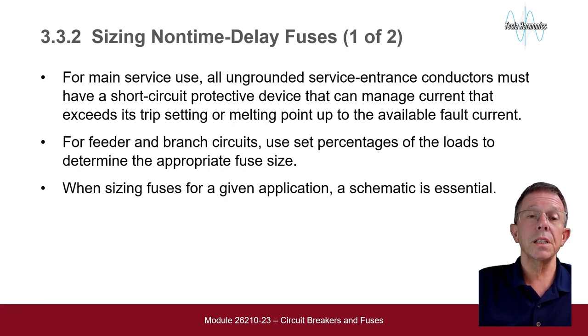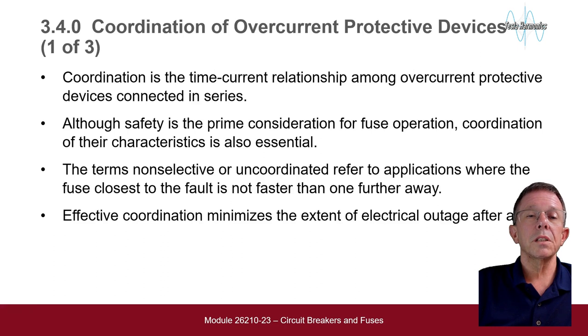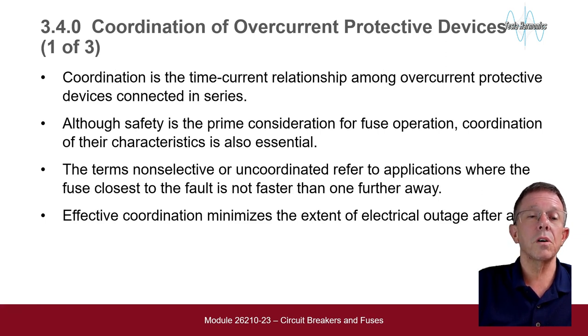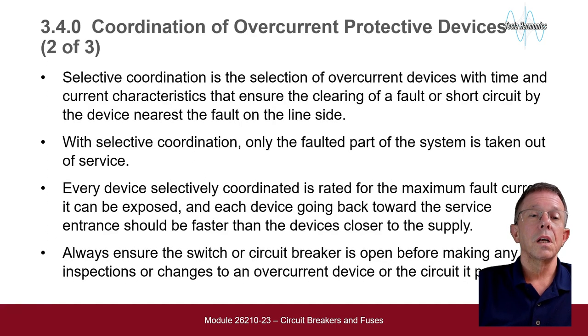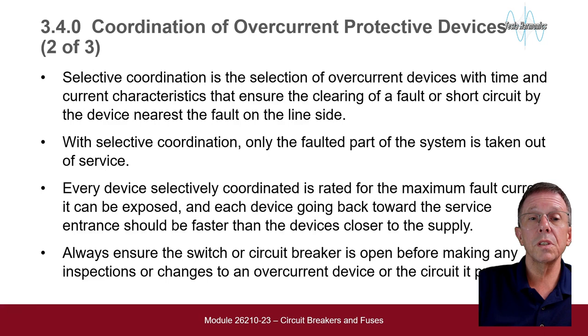Besides selecting the fuses for a given application, a schematic is essential. Coordination is a time relationship among overcurrent protective devices connected in series. Although safety is the prime consideration for fuse operation, coordination of their characteristics is also essential. The term non-selective or uncoordinated refers to applications where the fuse closest to the fault is not faster than one further away. Effective coordination minimizes the extent of electrical outage after a fault. Selective coordination is a selection of overcurrent devices with time and current characteristics that ensure the clearing of a fault or short circuit by the device nearest the fault on the line side. With selective coordination, only the faulty part of the system is taken out of service. Every device should be rated for the maximum fault current it can be exposed to, and each device going back toward the service entrance should be faster as it is closer to the supply.